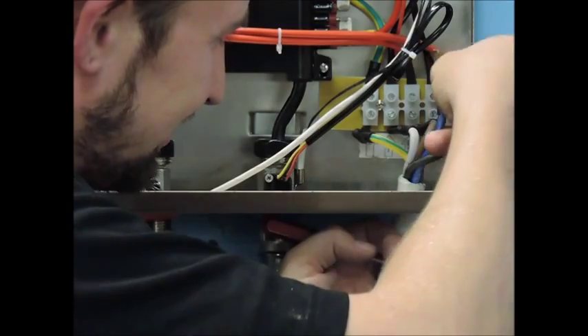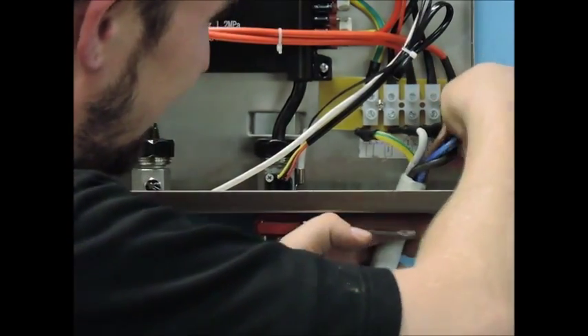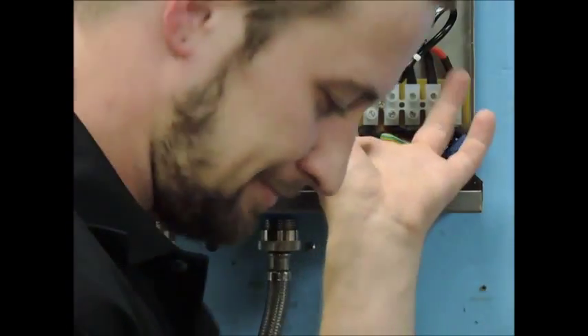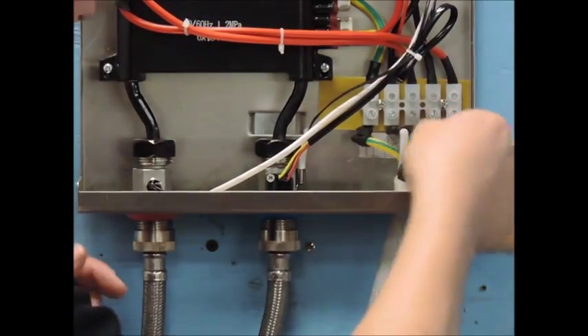Next, we have our first pair of power connections, and in our example, it will be the white and brown wires going into the first L1 and L2 terminals. These two wires will terminate at the same 50 amp double pole breaker for this model.